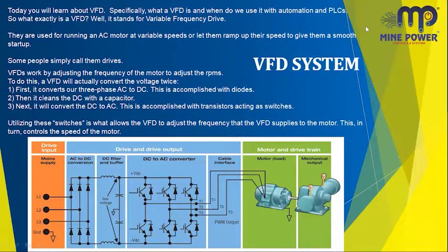You see the DC supply, positive and negative, goes to the DC to AC converter, which has 6 IGBTs. For a single phase, 2 IGBTs are needed to control the DC to AC. So 6 IGBTs are present, and the three-phase supply output goes to the motor, and the motor runs at various speeds. For conveyors, and also for motor protection, we can vary the speed to whatever speed we need.